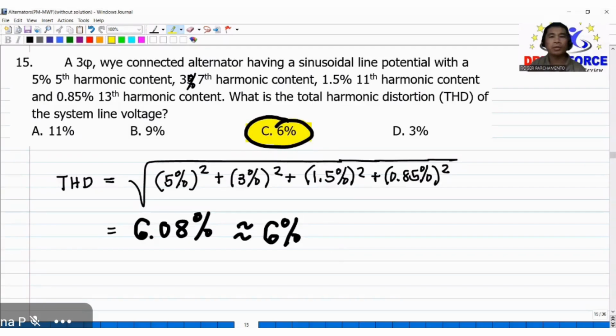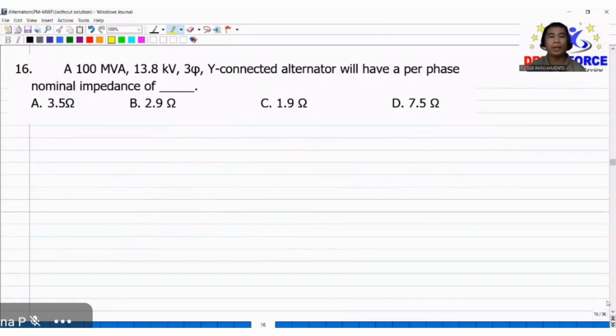So the total harmonic distortion of that sinusoidal line potential with those harmonic contents is 6%. Next, a 100 MVA 13.8 3-phase Y-connected alternator will have a per-phase nominal impedance of blank. Okay, so the nominal impedance calculated here. So this is Y-connected, Y per phase. So that will be equivalent to the kilovolt squared divided by the MVA.